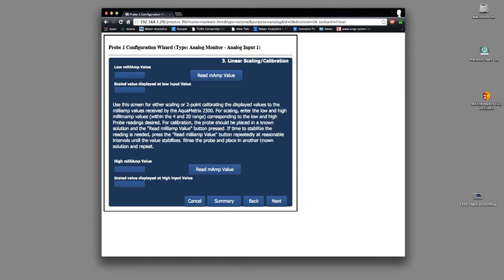This is where we calibrate. Calibration has never been easier. First, I'm going to put the probe in pH calibration solution. The big challenge in calibrating any pH probe is knowing when the probe output value settles down so that you can lock in the reading.